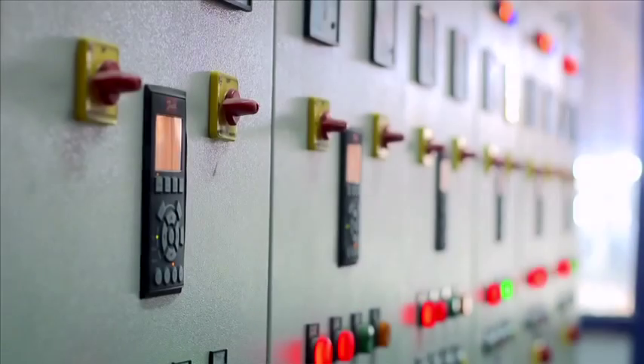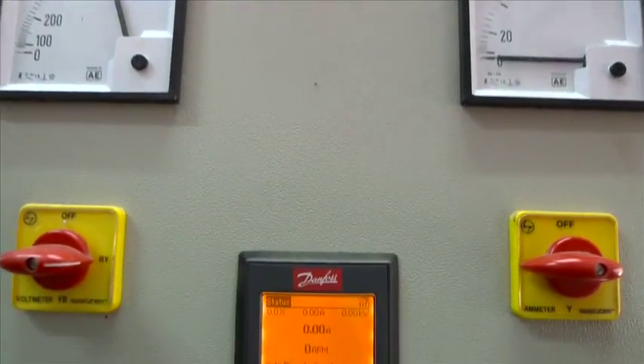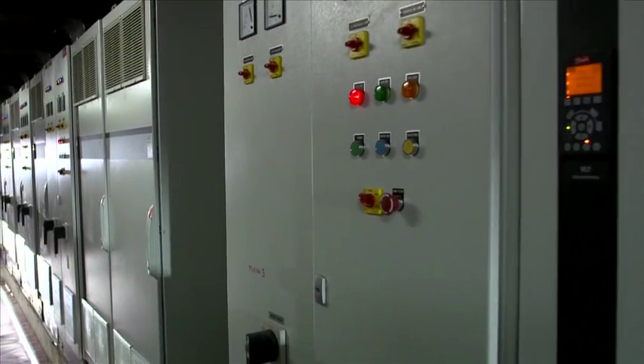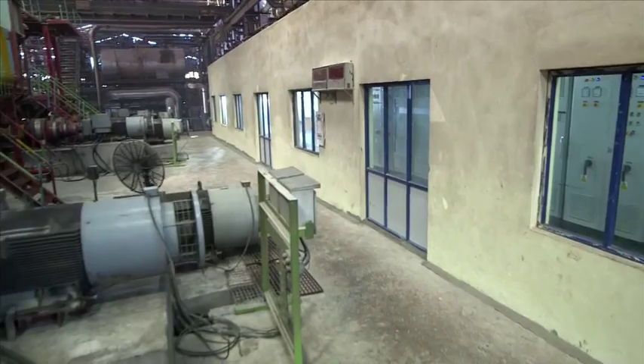Two years back, we started our sugar factory capacity expansion and modernization project. We decided to change steam turbine drives to electrical drives for mill application. Basic requirement for this purpose was 12-pulse drive to maintain harmonics level in electrical system. There were many installations of Danfoss. We verified the installations and discussed the operational parameters they are getting from Danfoss VFD drives. At that time, we decided to go for Danfoss. Pre-sales support is also good, and the after-sales service team of Danfoss is very good. Since last 2 years, drives are in operation. Performance-wise, drives are very good, trouble-free, and downtime on account of drives is nil.